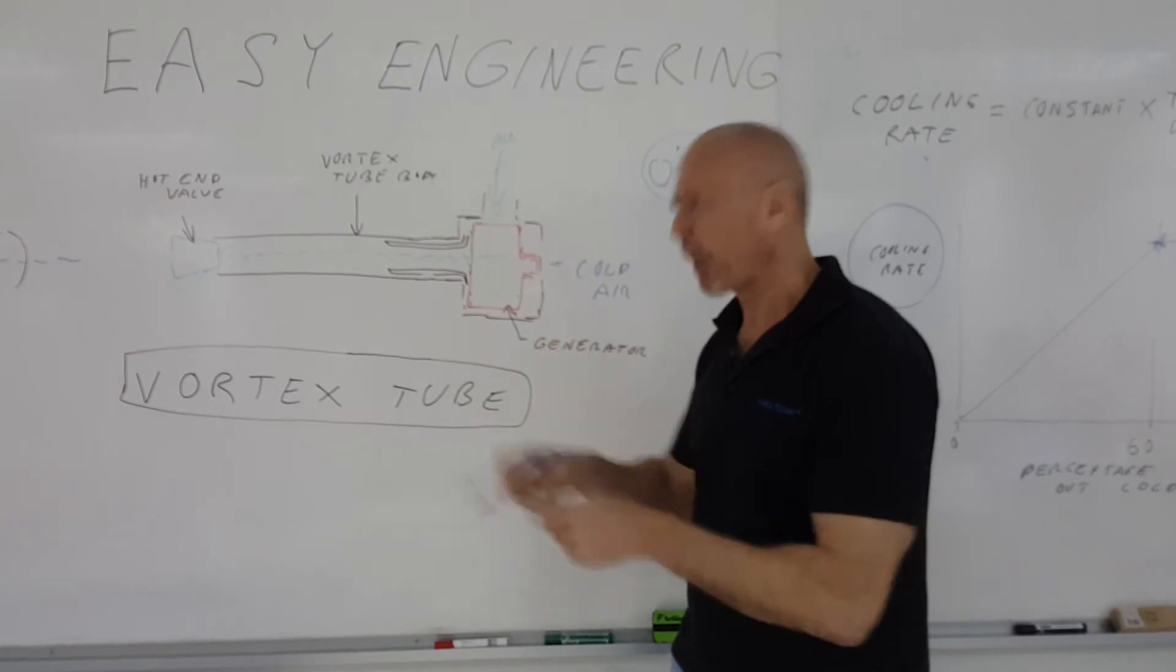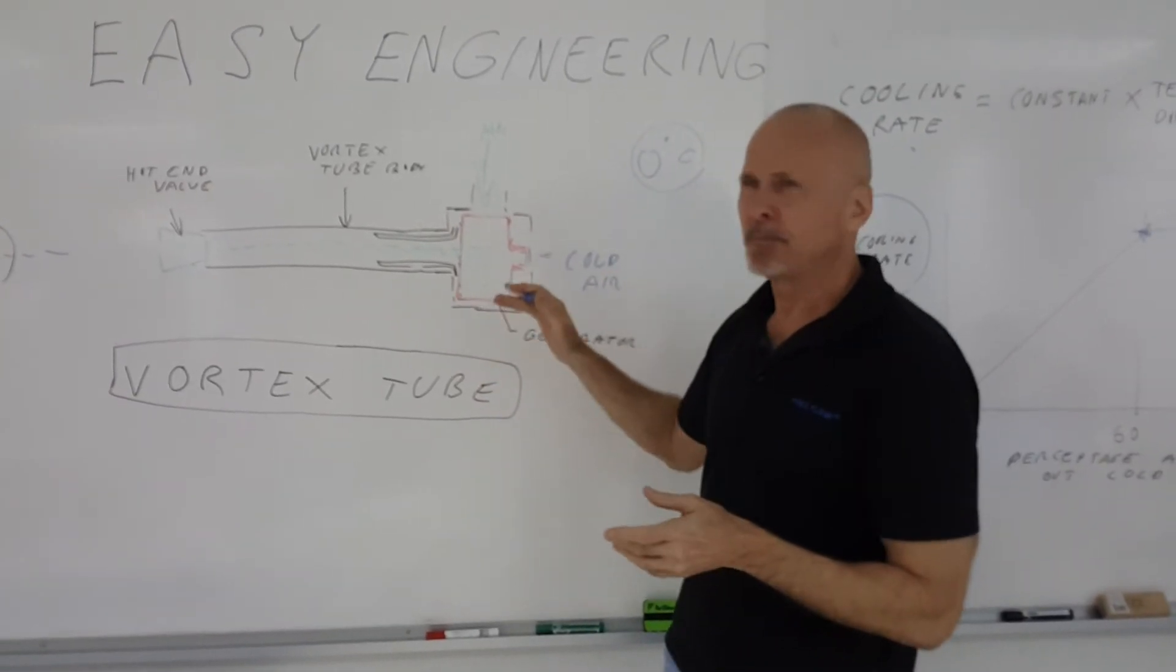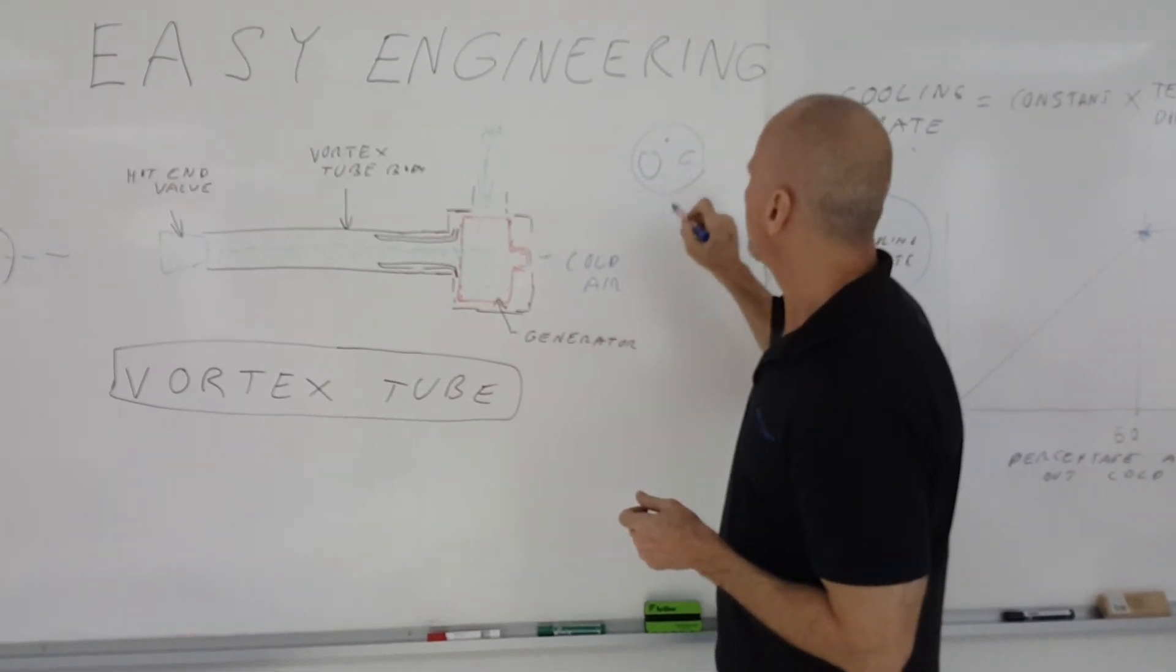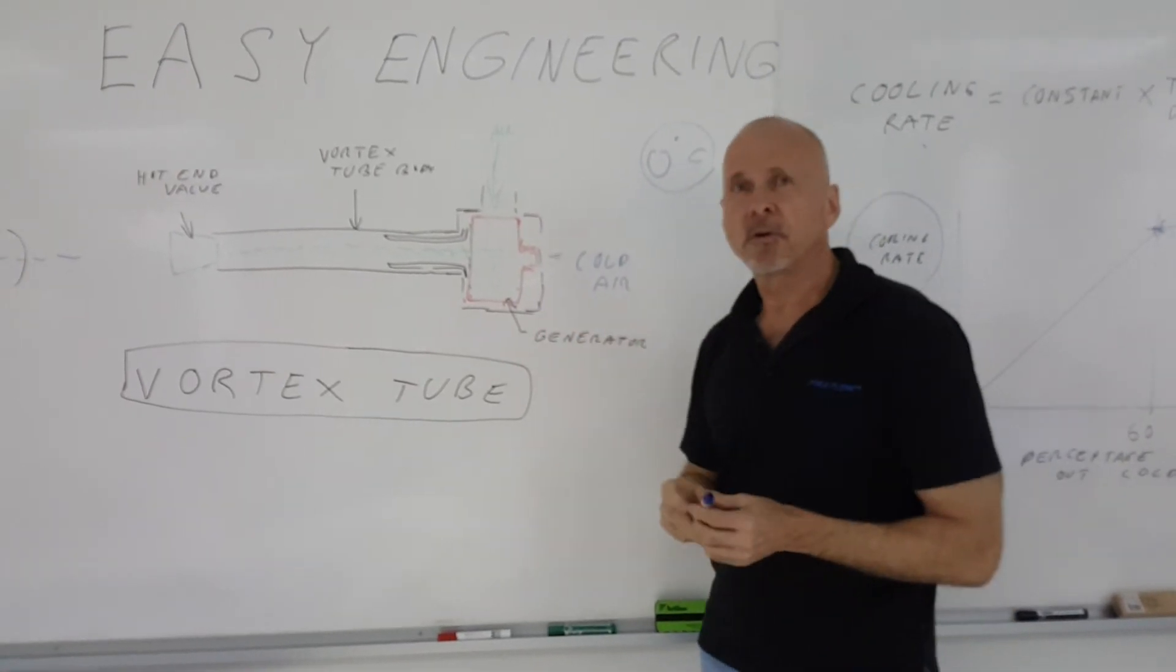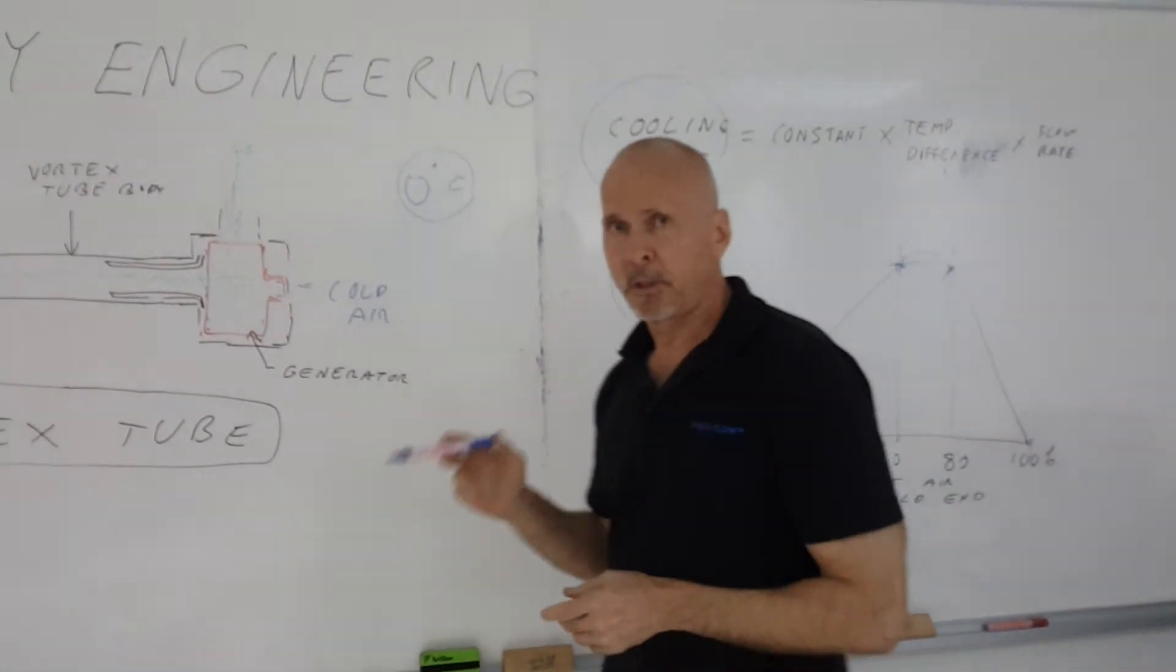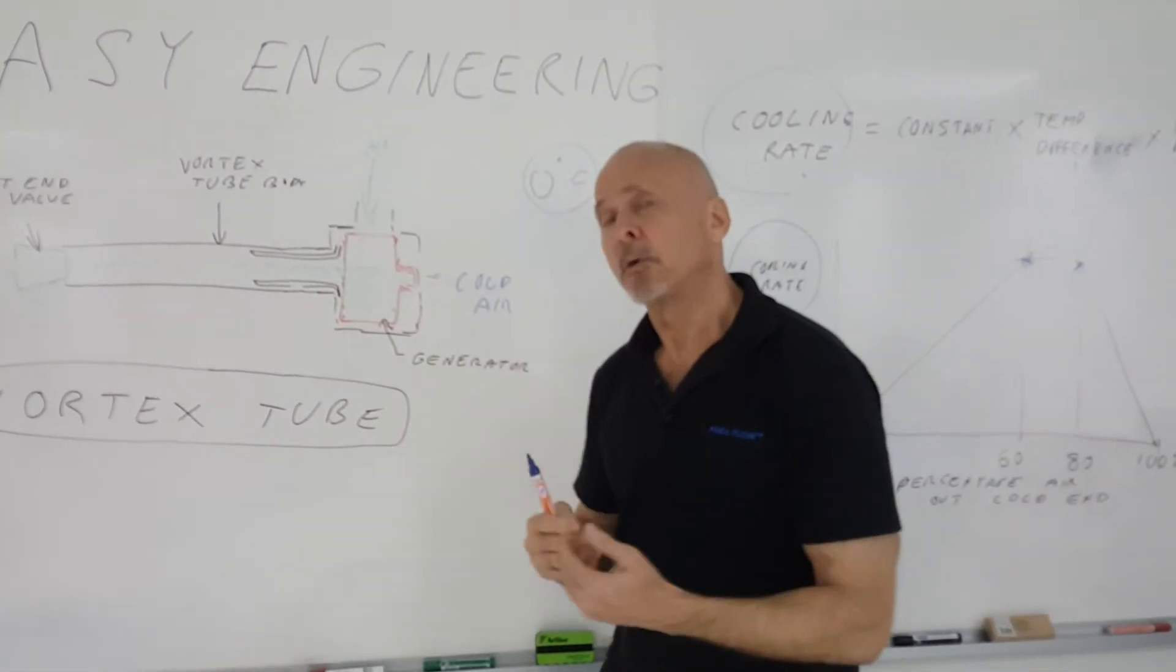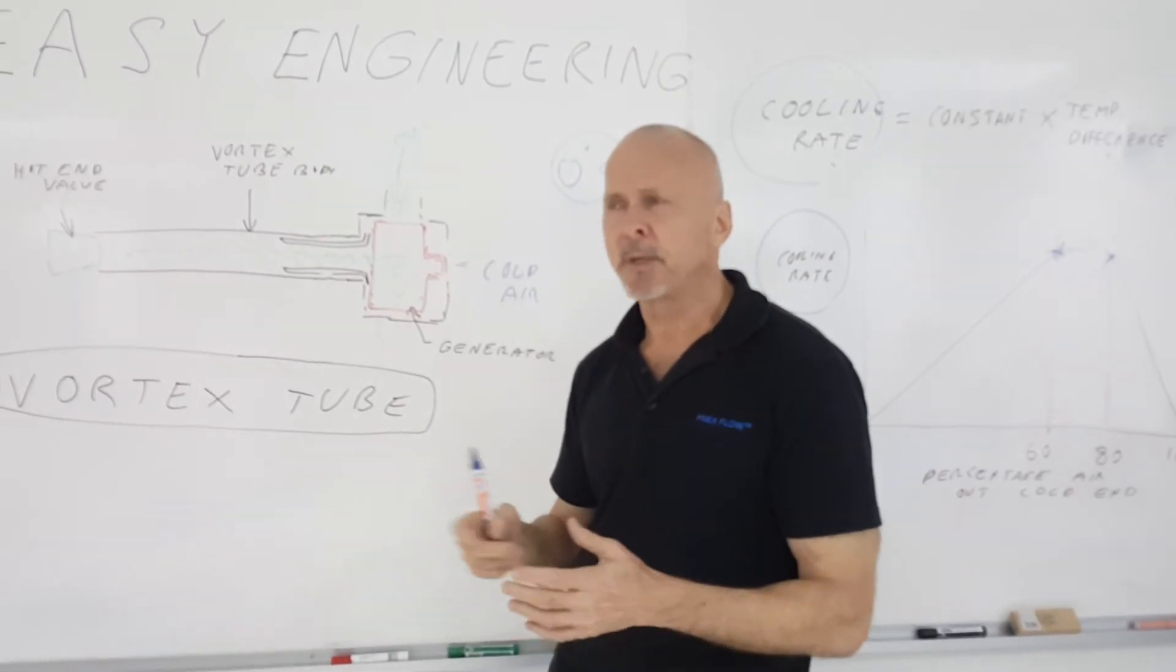It kind of goes like, you know, just pops out. It's quite funny and they'll start up again. But you really don't want to have that. You want the vortex tube constantly running. So actually having the temperature around zero to plus two degrees Celsius or somewhere in that range is actually a very good way to operate the vortex tube for getting that maximum cooling rate. And as I explained before with the example of the bowl of soup, you want not only cold temperature, you want a flow rate that's reasonable to do the cooling. You want an optimum cooling rate.